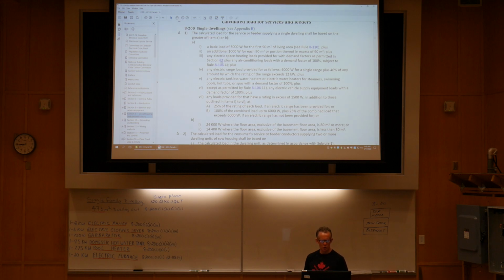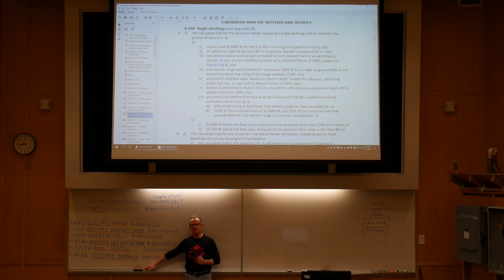That is why there's a quote to the rule in section 62. The Rule 8-106 sub-Rule 4 is a demand factor rule, and what it allows us to do, if we had an electric furnace and an air conditioning, generally, your summertime, you have your air conditioning on and your heat off.